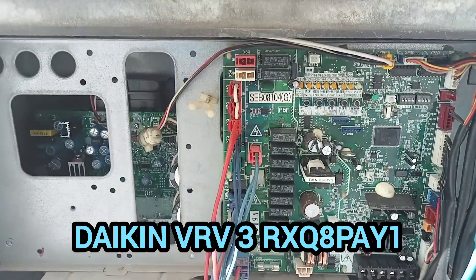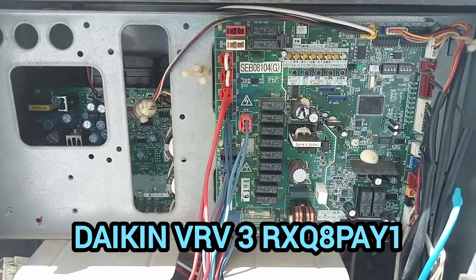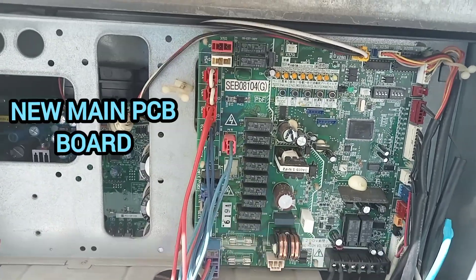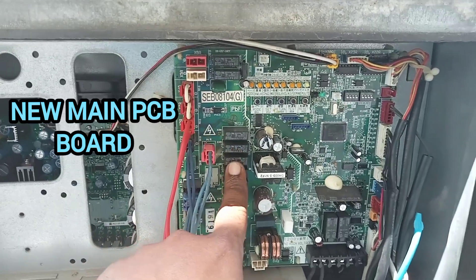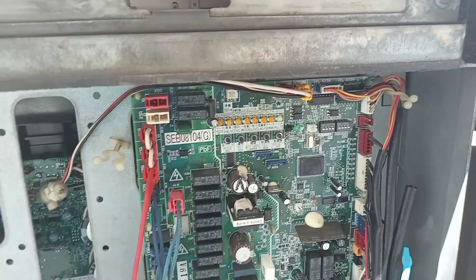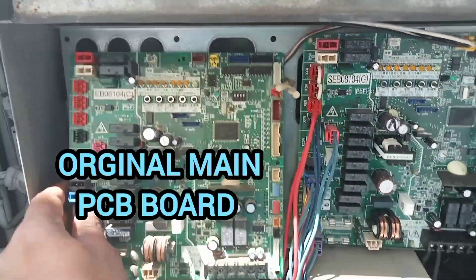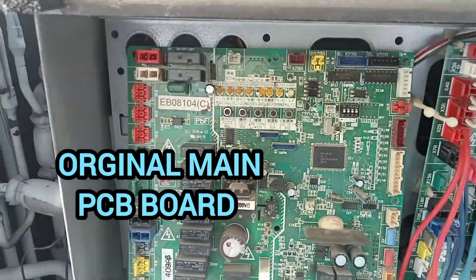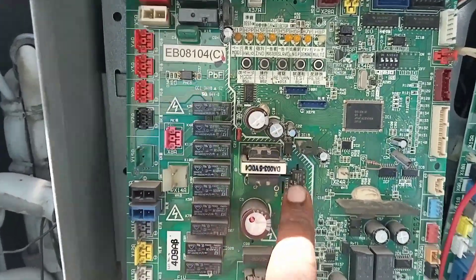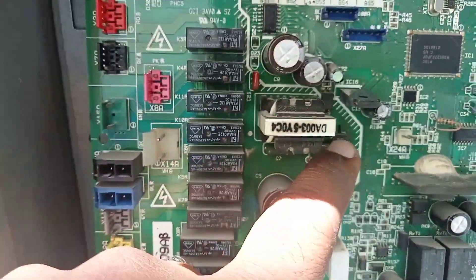This is the VRV3 RXQ8PAY1 model. We just replaced the main PCB board. This is the new PCB board, and this is the original PCB board. The reason for replacement is that the IC here was short circuited.